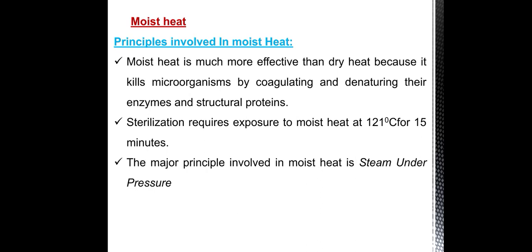Moist heat: the principle involved in moist heat. Moist heat is much more effective than dry heat because it kills microorganisms by coagulating and denaturing the enzymes and structural proteins. Sterilization requires exposure to moist heat at 121 degree Celsius for 15 minutes. The major principle involved is steam under pressure.